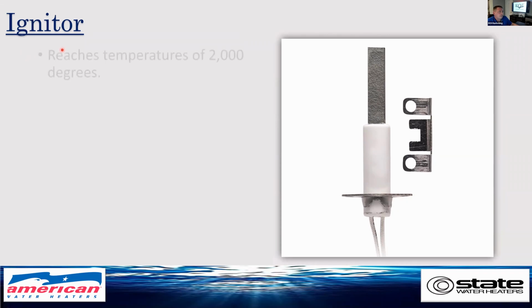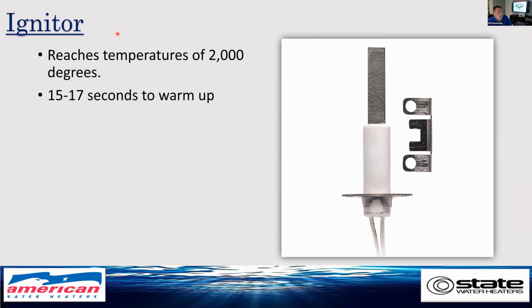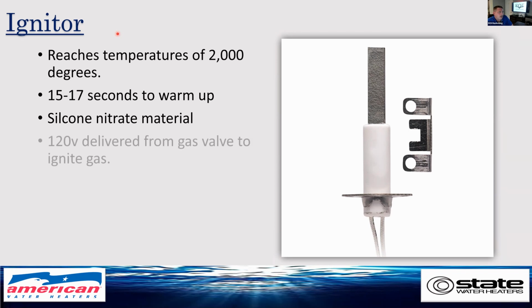The igniter. The igniter reaches temperatures of 2,000 degrees. It takes about 15 to 17 seconds for it to warm up. It's made from a silicon nitride material. 120 volts is delivered from the gas valve to the igniter to ignite the gas.